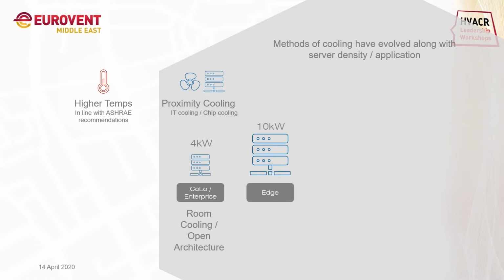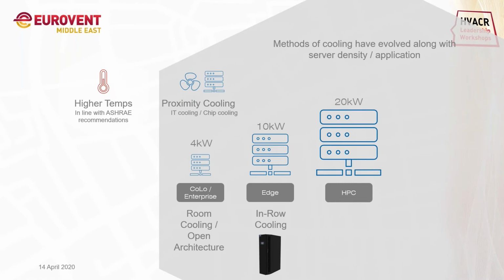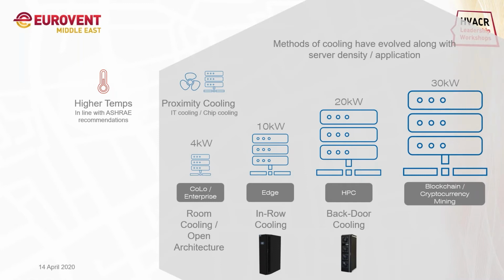In edge computing, we are using a 10 kilowatt server density, where we are using in-row cooling, that's rack cooling systems. So in high performance computing applications, we are using even higher 20 kilowatt server densities, where we use backdoor cooling or on-rack systems. In blockchain or cryptocurrency mining applications, we even see a much bigger server density of 30 kilowatt, where we use direct chip cooling, the latest one.